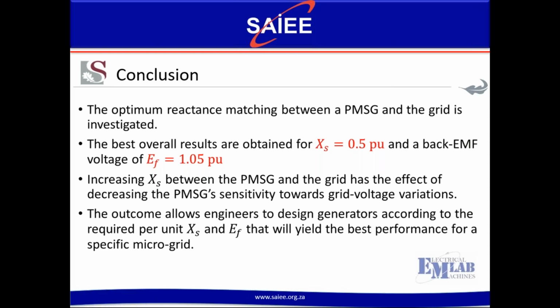The best overall results are obtained for a synchronous reactance of 0.5 per unit and a back EMF voltage of around 1.05 per unit. It was also found that increasing the synchronous reactance between the generator and the grid has the effect of decreasing the generator's sensitivity towards grid voltage variations. This outcome allows engineers to design generators according to the required per unit synchronous reactance and back EMF voltage values that will yield the best results for a specific microgrid.